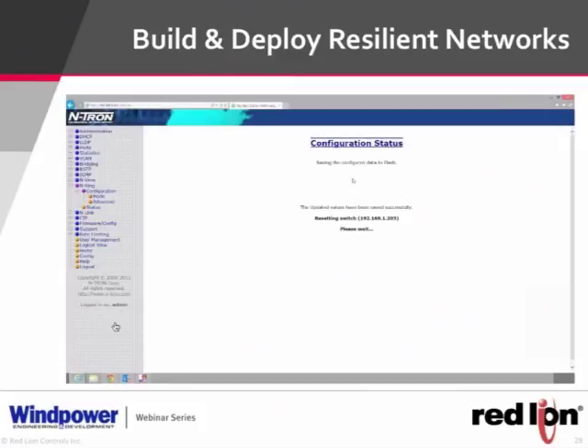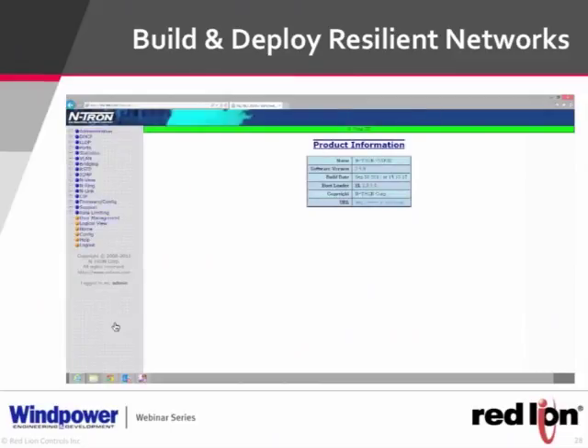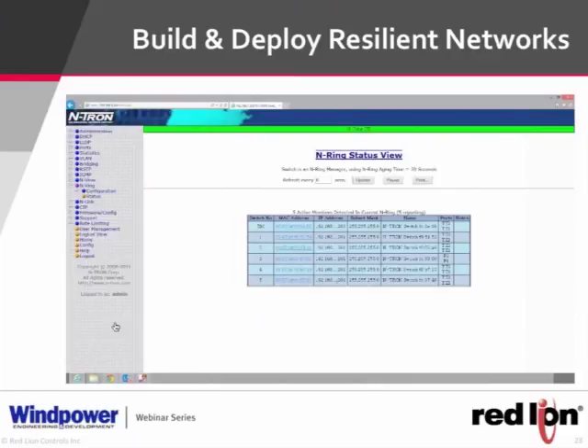With industry-standard RAPS/RSTP, if a ring failure occurred you'd have no way to tell exactly where it happened. With N-Ring, the ring manager shows a green status indicator confirming the ring is intact. If any outage occurs, it turns red. The page also displays the number of switches in the ring and the IP addresses. This is how little time it takes to set up N-Ring.